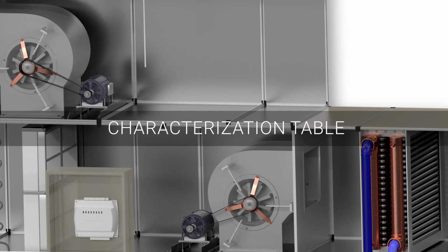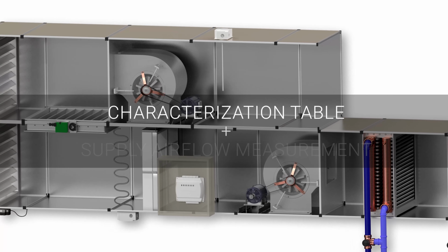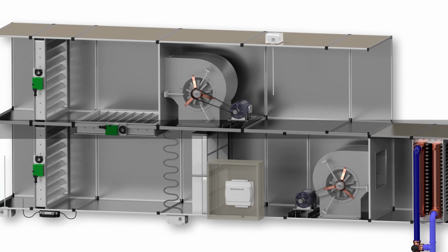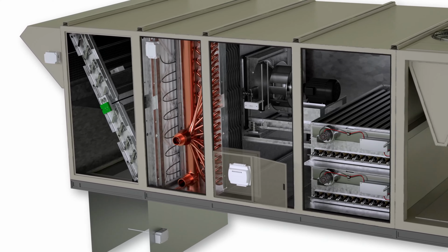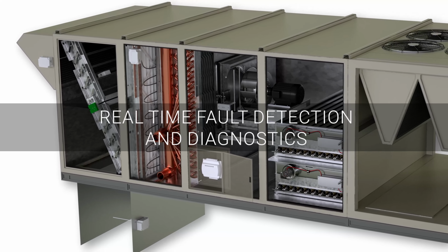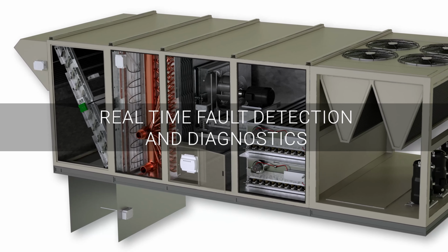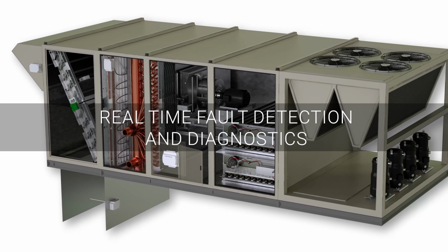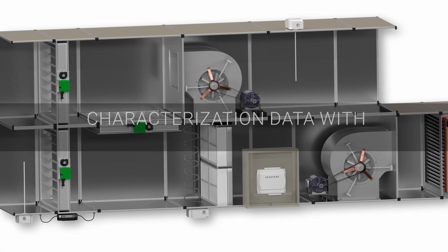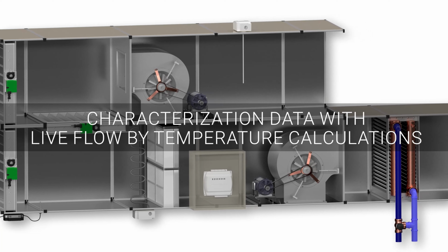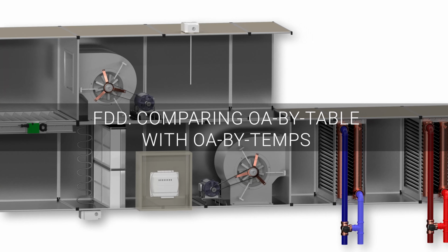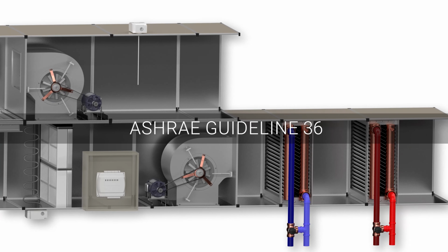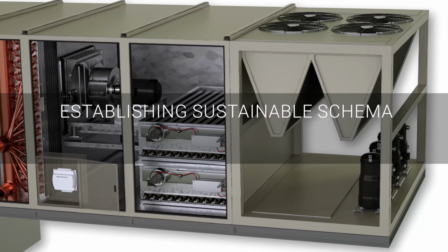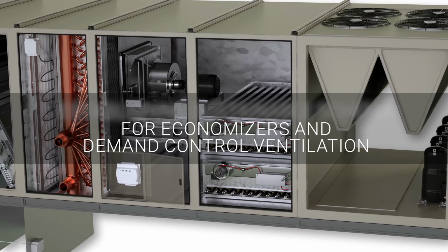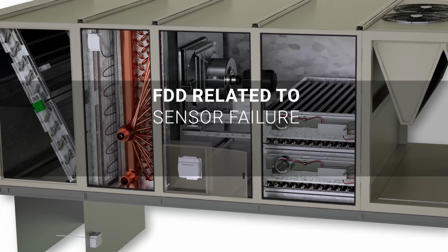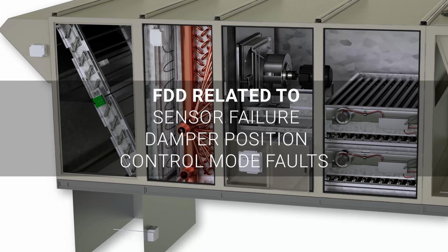After the table is obtained, the outside and return airflow rates are known from the characterization table and the supply airflow measurement. However, leaving the temperature sensors in place allows the AFMS to deliver a set of powerful, real-time fault detection and diagnostic capabilities, ensuring that you know if there are any issues with your building's mechanical system. By actively comparing the characterization data with live flow-by-temperature calculations, the AFMS can detect changes in the system's mechanical performance. This makes meeting ASHRAE Guideline 36 items possible, including establishing sustainable schema for economizers and demand control ventilation. Additional FDD related to sensor failures, damper position, or control mode faults are also available.